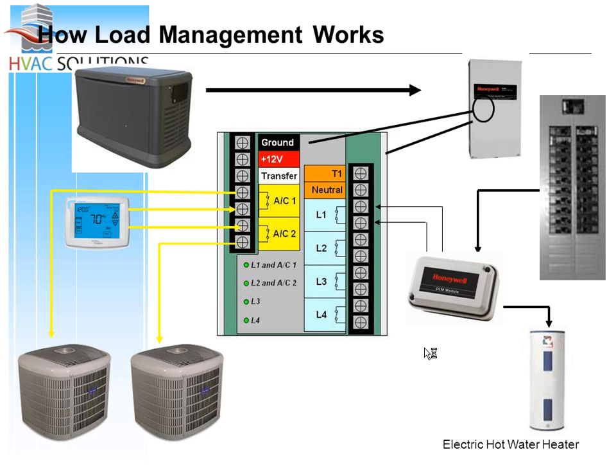Then it goes to this circuit board inside of the transfer switch, and it looks at AC1, and it says, does that generator have enough power to turn on AC1? It does, so it kicks it on. Then it goes over to L1. Now, the difference between L1 and AC1 is that AC1 is a 24-volt circuit—all we're doing is cutting or breaking the Y wire so that we're allowing the thermostat to make a call. At L1, we are dealing with what I'm going to call 120-volt contacts.